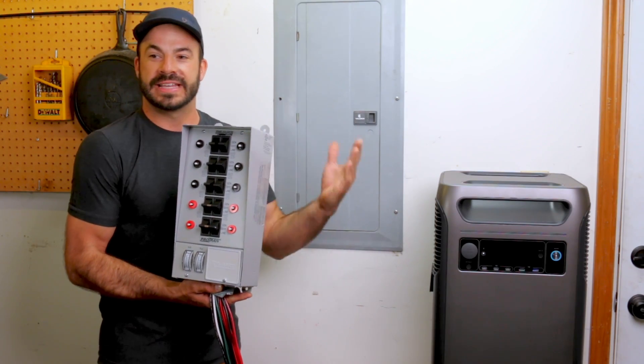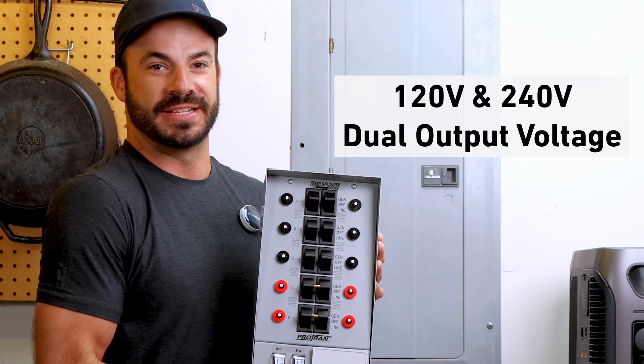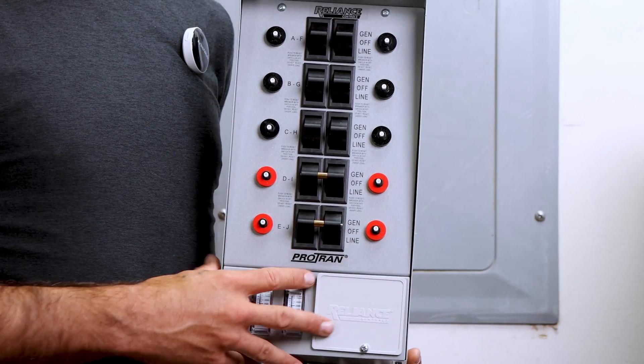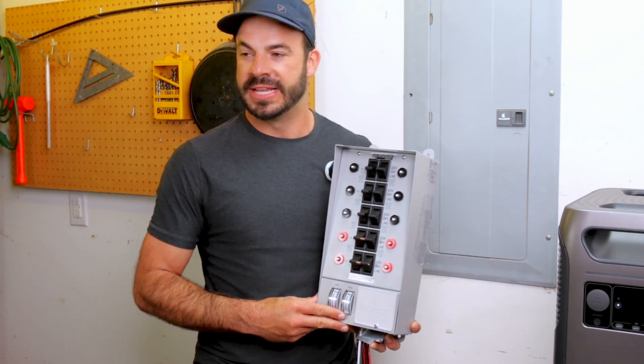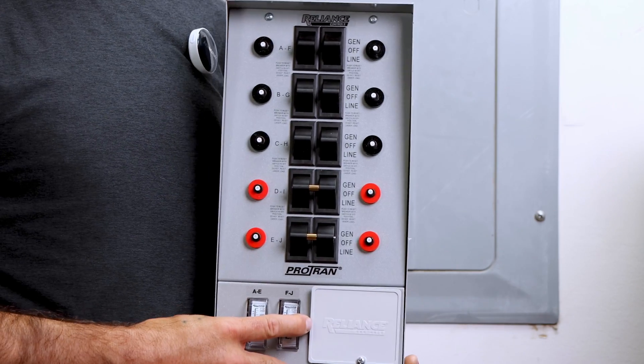Unlike conventional small gas power generators, the Solix F3800 is capable of producing 240 volt AC power, which means we can power large high-draw devices much easier. Because of that 240 volt capability, it's important to pick a transfer switch that can accept that type of incoming power. We're using the Protran transfer switch from Reliance Controls, which has two sides each receiving one of the 120 volt AC legs from the Solix F3800.